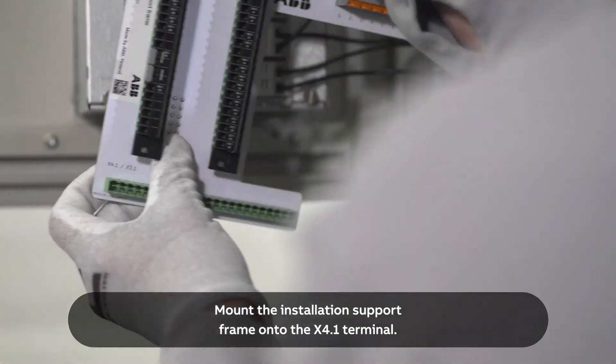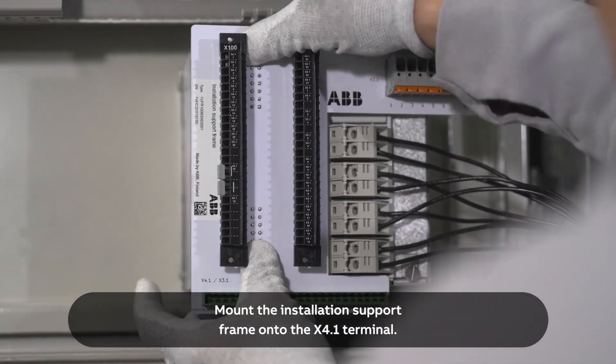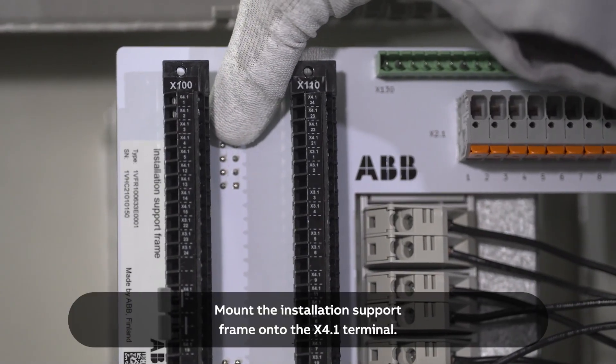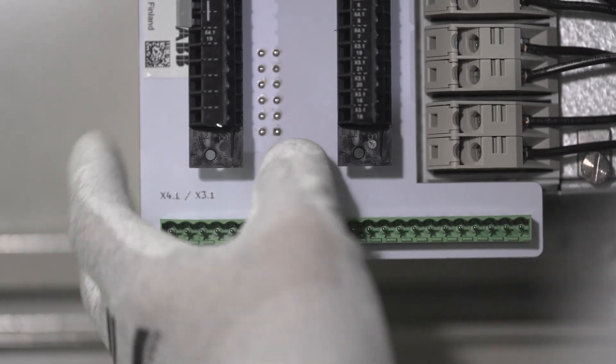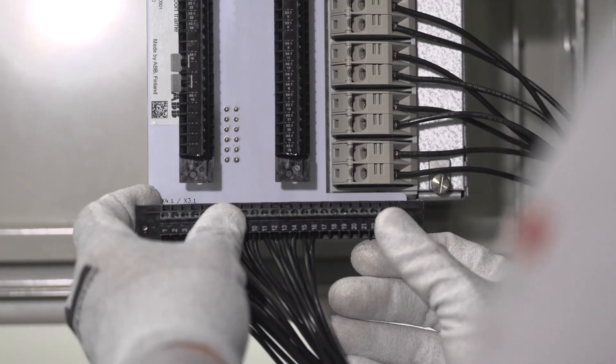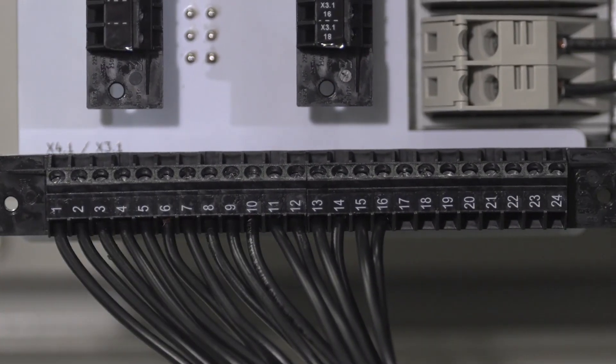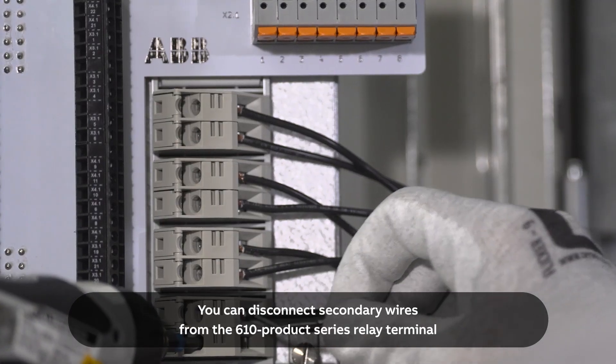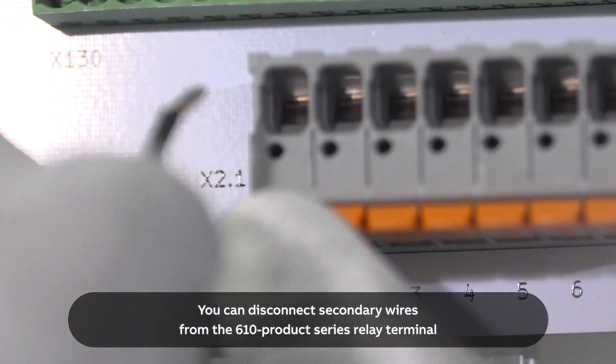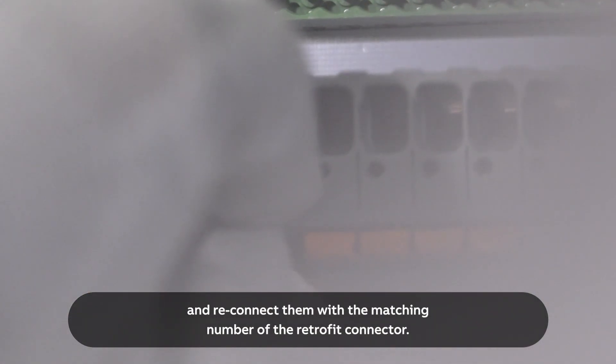Mount the installation support frame onto the X4.1 terminal. The retrofit connector is marked with numbers on top. You can disconnect secondary wires from the 610 product series relay terminal, and reconnect them with the matching number of the retrofit connector.